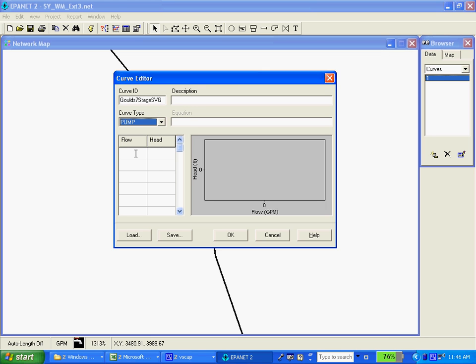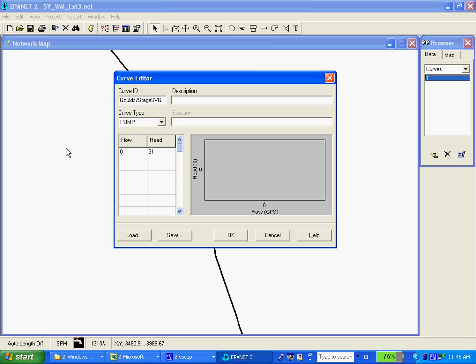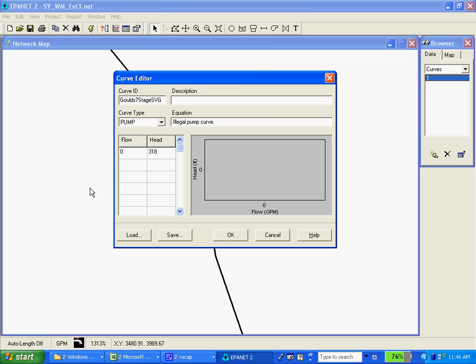So I'm just going to go ahead and start entering the pump curve and this is using information straight from a manufacturer's literature of the pump curve starting with 0. The static pumping rate is 318 feet of head. Keep in mind that we selected with this model to use gallons per minute and feet for our units although it doesn't actually display them here.